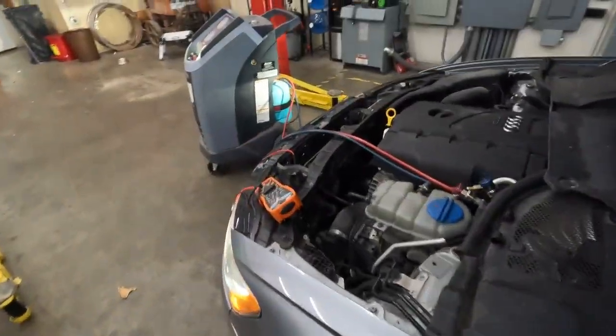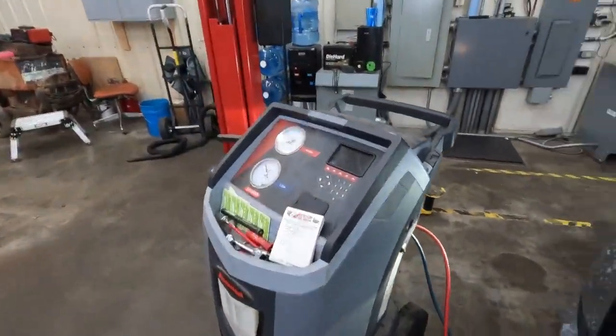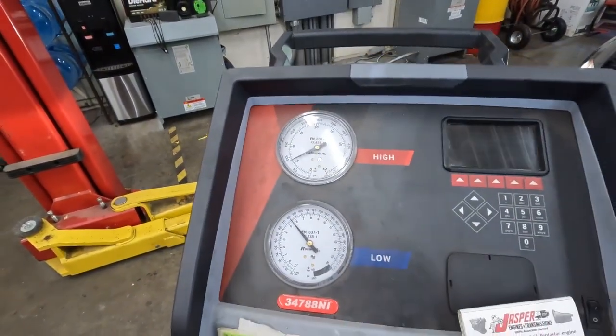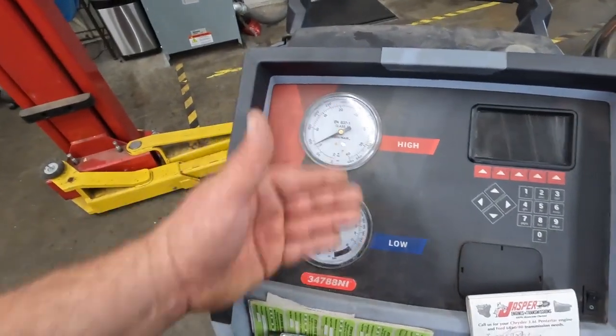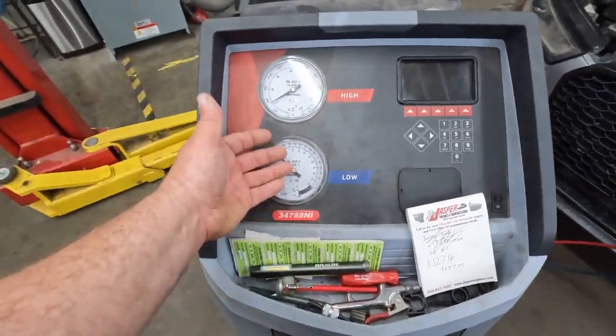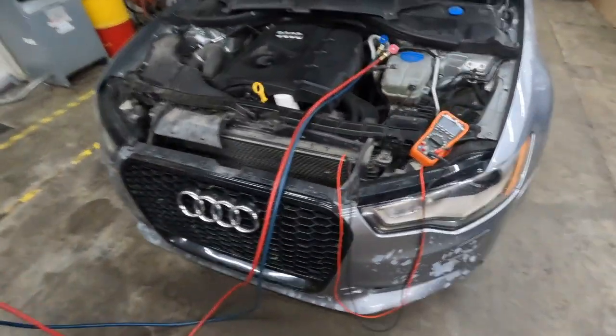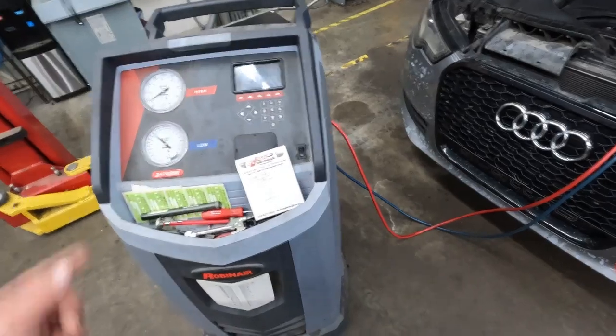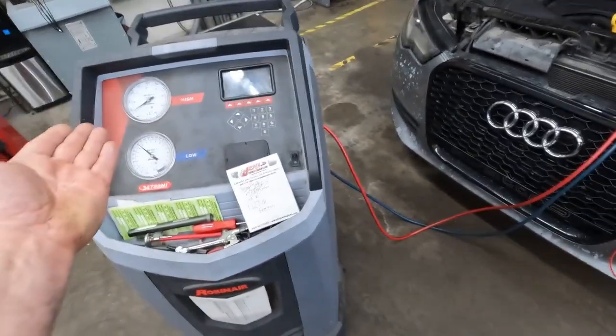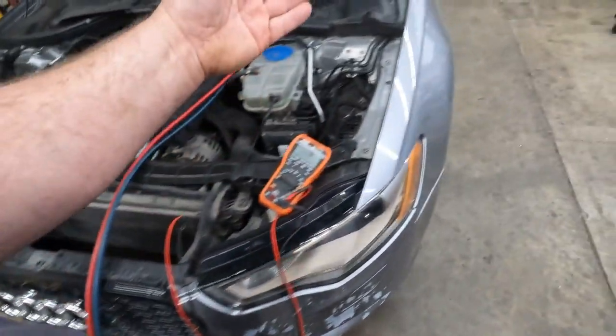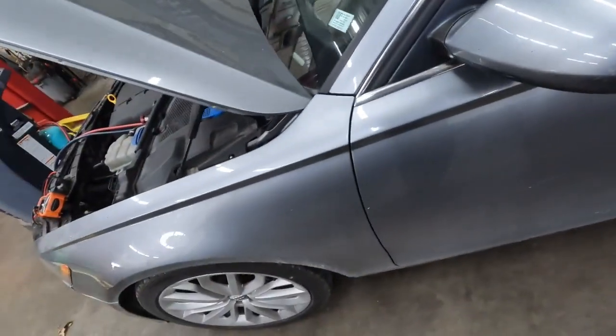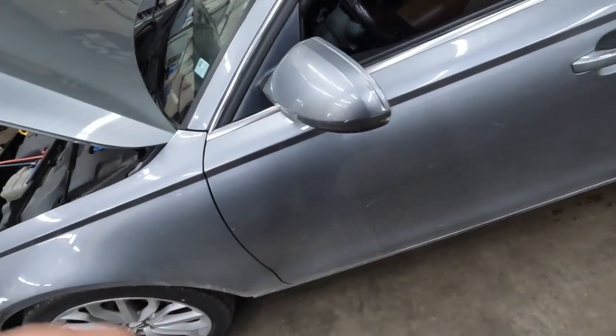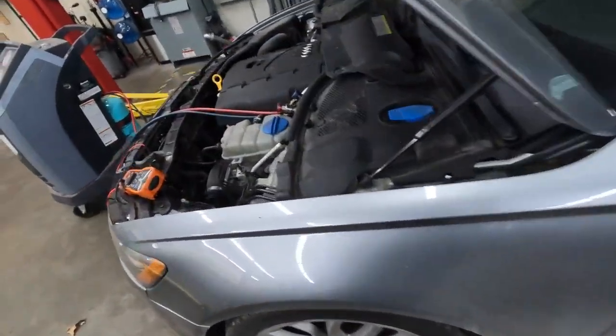So first thing we want to do is hook up our AC machine and check the pressures. Well, we've got more than half a bar - we see that we have 80 psi in the system, which is what we'd expect to see at about 70 degrees in here. So we know we have Freon in the system. We know that less than half a bar is less than 7 pounds of pressure, so that sensor is saying we have basically no pressure in the system.